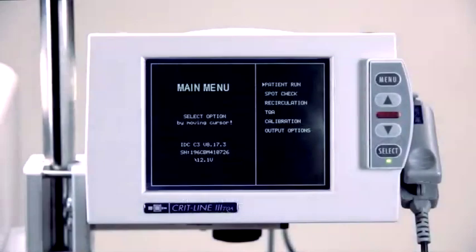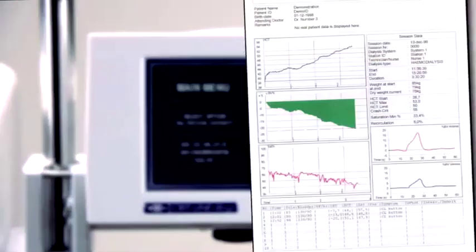The Crit-Line monitor provides a significant amount of treatment data. A treatment profile will include hematocrit, blood volume change, and oxygen saturation profiles all on one sheet of paper. The header information above the profiles will include the patient's name and ID number if entered into the Crit-Line monitor prior to treatment. In addition, the header information includes the patient's starting hematocrit, maximum hematocrit, hematocrit limit if entered, starting hemoglobin, station number if entered, date of treatment, along with the start time and end time of the treatment.